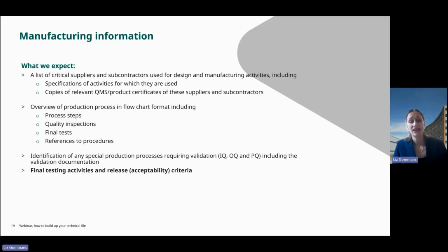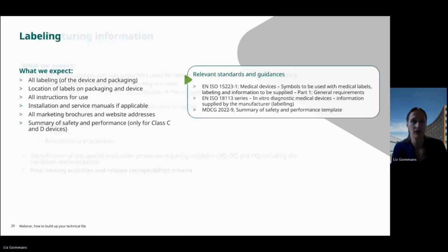And then, very important, we would like to see the final testing activities and release criteria. So before your batch is released, what do you do? How do you verify it? This is often forgotten actually, but we really expect to have this information in the technical file.